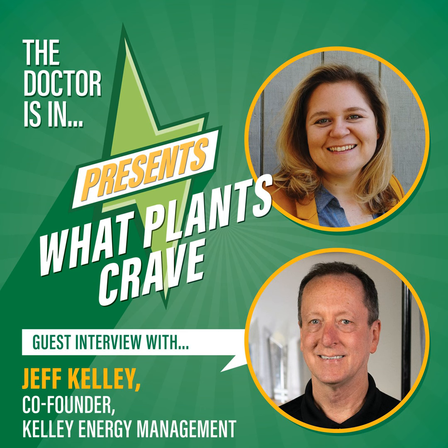I would love to see somebody do that on paper and see what it would do, because it would definitely make your system smaller, wouldn't it? You'd only have half the lights on at any given time. Also, if you design from the ground up with half the lights on, your switch gear and transformers, everything can be sized smaller because the plan is not to operate it all concurrently. And utilities are well aware of that.